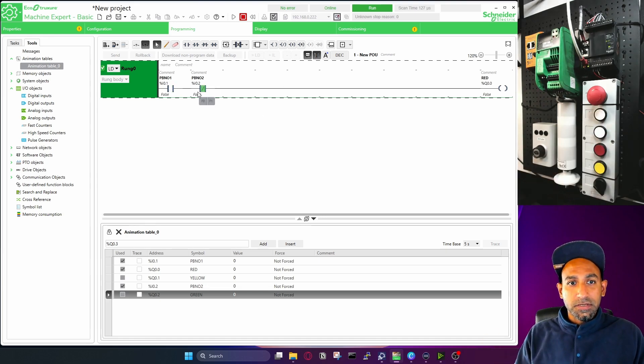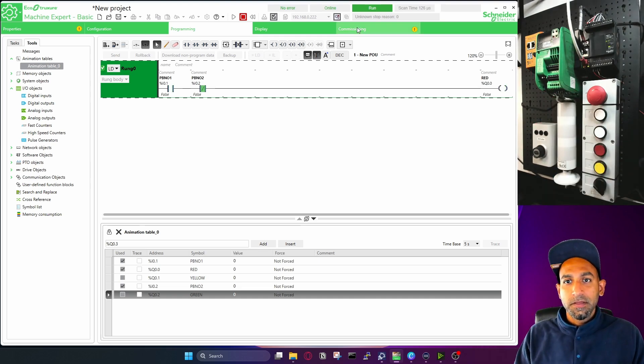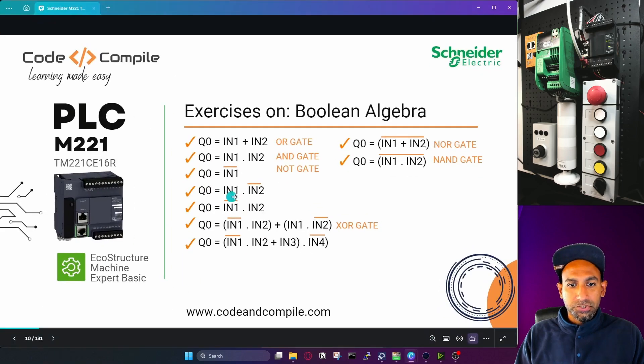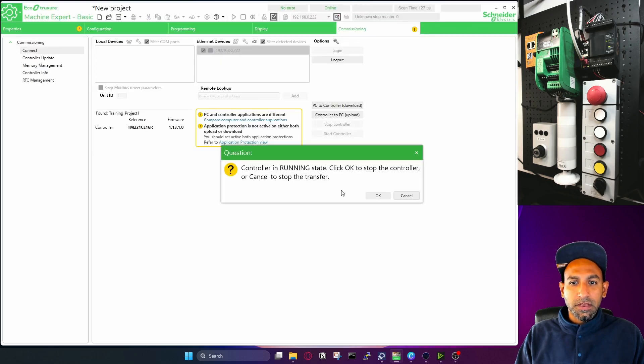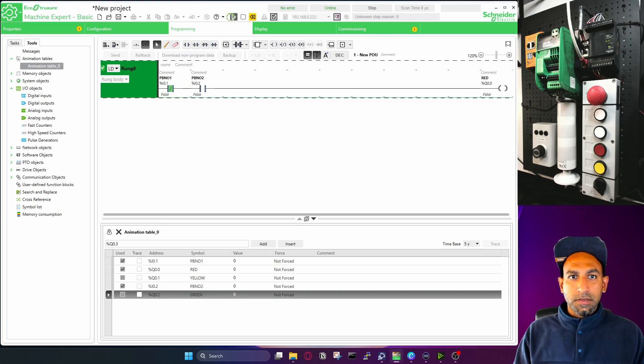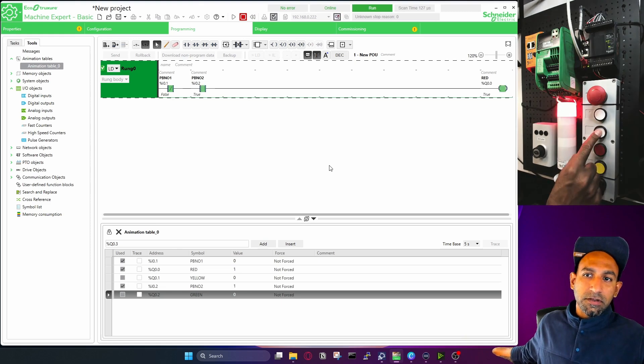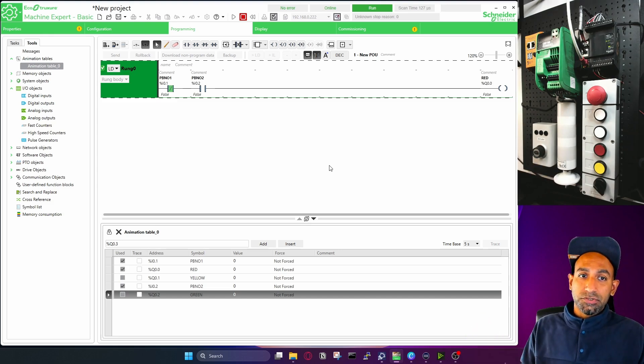If I reverse the situation and put the negate on IN1 instead, then the output will be true only if IN1 is false and IN2 is true. I take the negate on I0.1 and download. Now the output is true only when I press IN2. IN1 I don't have to press because it's already negated, already sending a true signal. If I press IN1, it will be false. So if I press both inputs, output is false. Output is on only if IN2 is true.